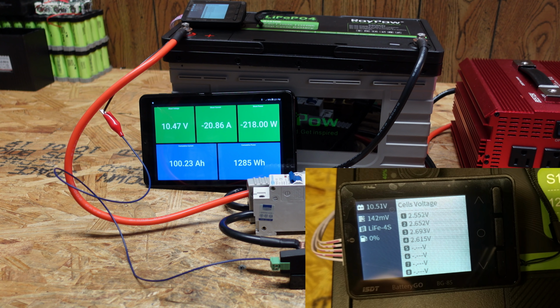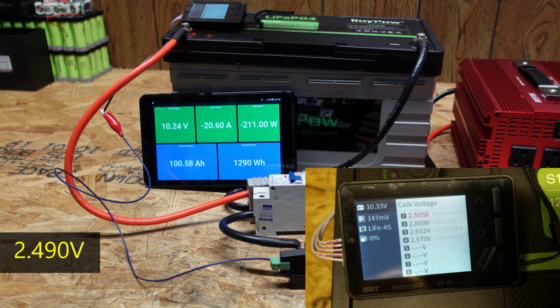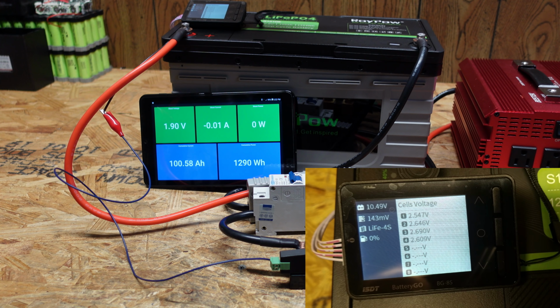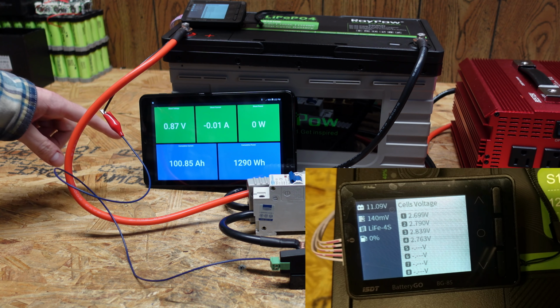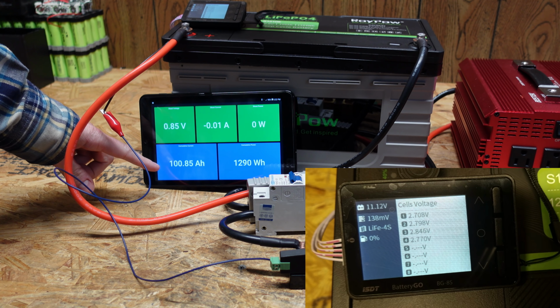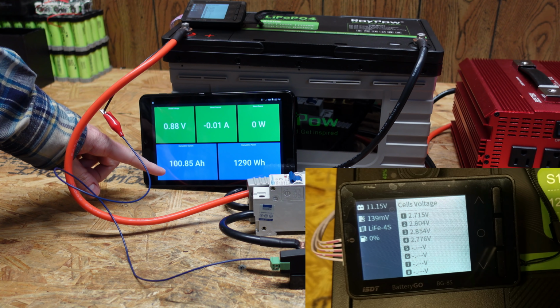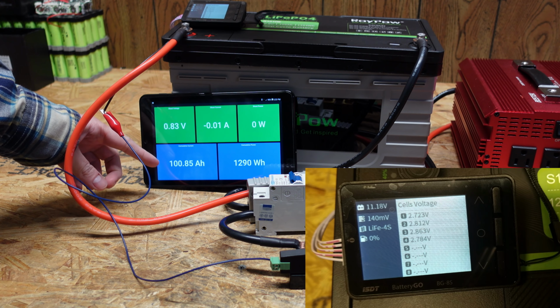Alright, so we're approaching 2.50 volts with a spread of 143 millivolts. Cell number 1 has dropped below 2.5 and the BMS shut off pretty quickly, so that was pretty accurate at the low end, but we're seeing around 150 millivolts of difference. So I see the final metered capacity is 100.85 amp hours, and that's around the same, slightly lower than our first test.